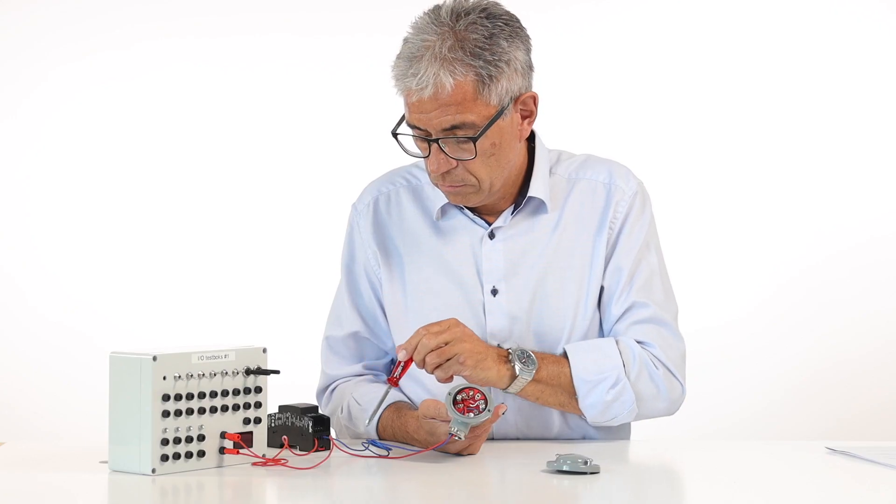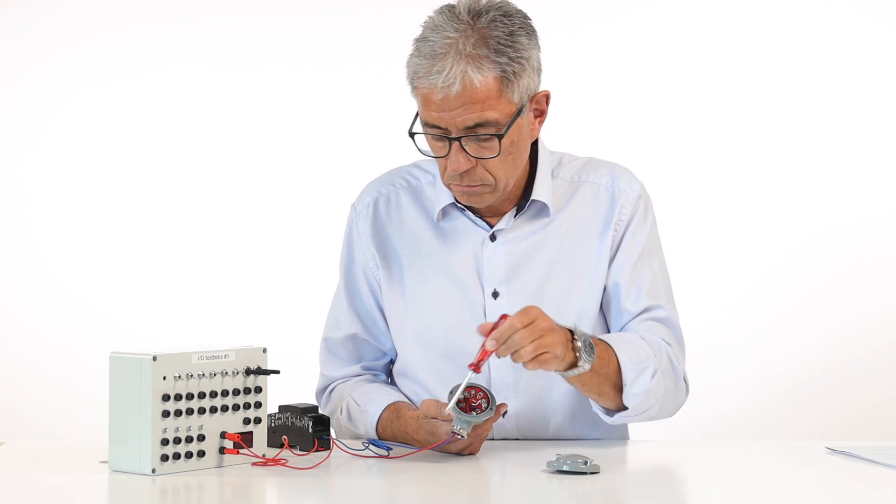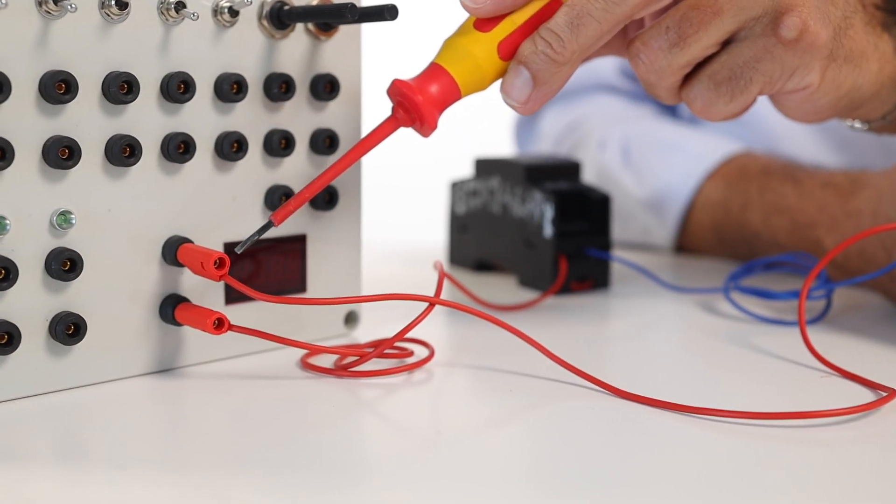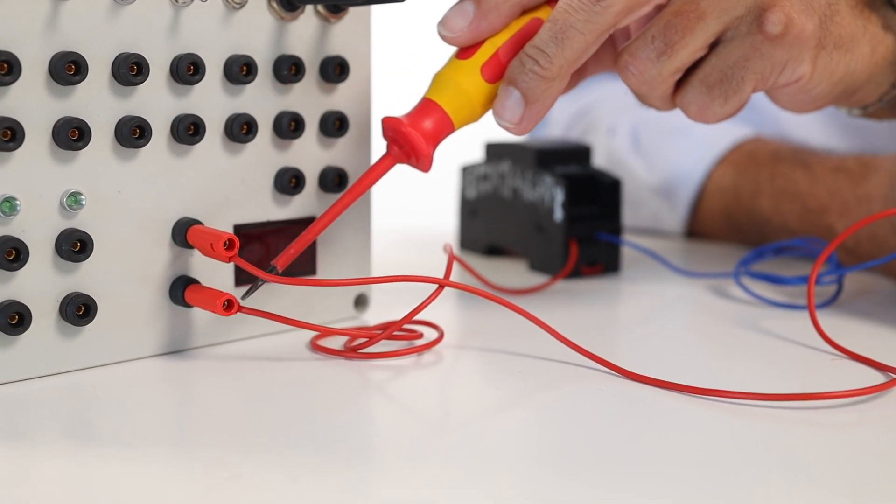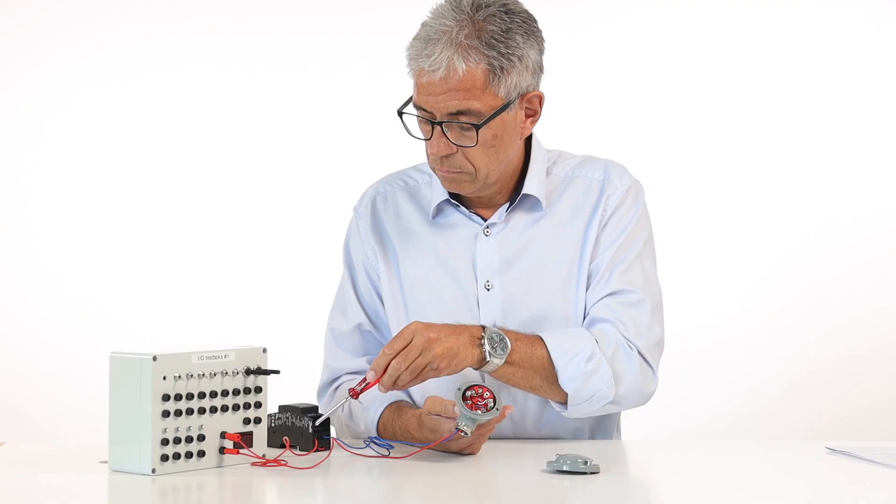The positive cord is connected from the transformer to the temperature transmitter. From the temperature transmitter, the negative cord is connected to the milliamp display in series. From the milliamp display, the cord is connected back to the negative power supply.